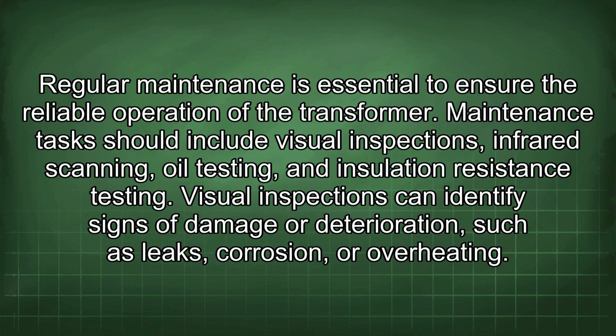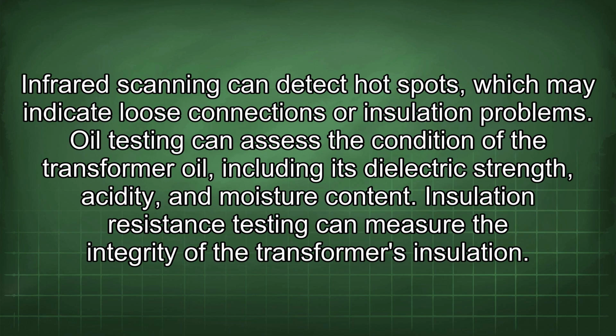Visual inspections can identify signs of damage or deterioration such as leaks, corrosion, or overheating. Infrared scanning can detect hot spots, which may indicate loose connections or insulation problems. Oil testing can assess the condition of the transformer oil, including its dielectric strength, acidity, and moisture content. Insulation resistance testing can measure the integrity of the transformer's insulation.